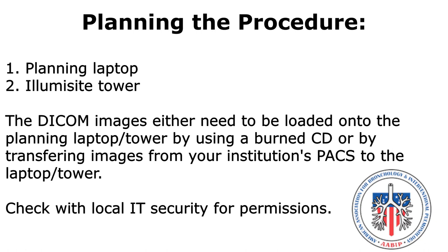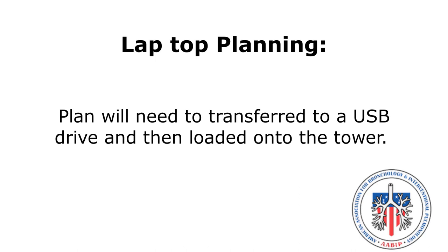The procedure may be planned on the planning laptop or the Illumisite tower. The DICOM images either need to be loaded onto the planning laptop or tower by using a burned CD or by transferring images from your institution's PACS to the laptop or tower. Check with local IT security for permissions. In this example, a planning laptop is used.